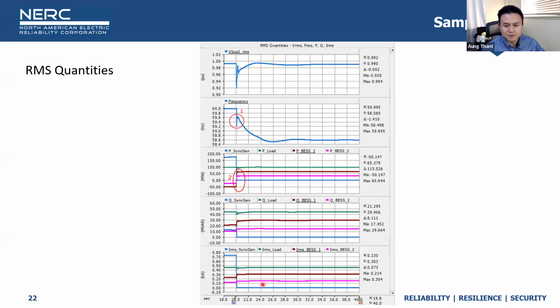The RMS current. Here we're plotting about 20 seconds post trip. This depends on what you want to see, that it's settling. However long it takes, you want to wait and make sure that it doesn't start growing again. So although I'm showing 40 seconds here, you actually want to run as long as you keep seeing oscillations and make sure that it doesn't blow up, say 60 seconds later.